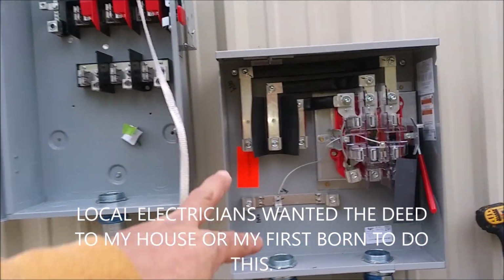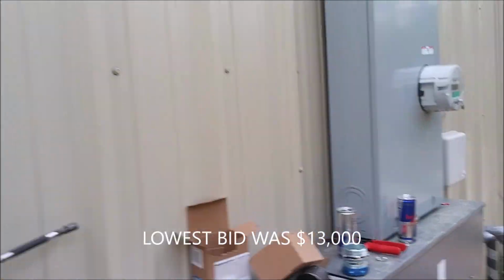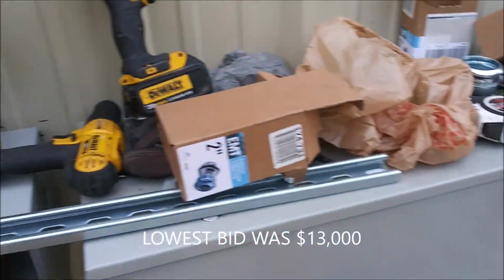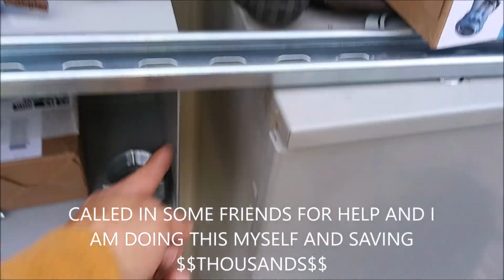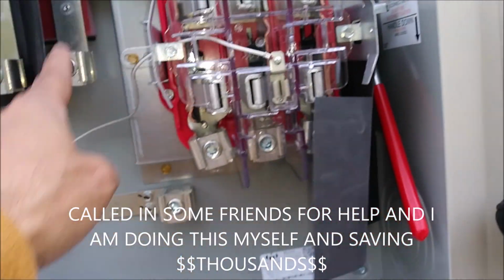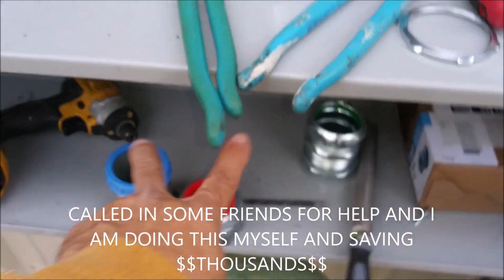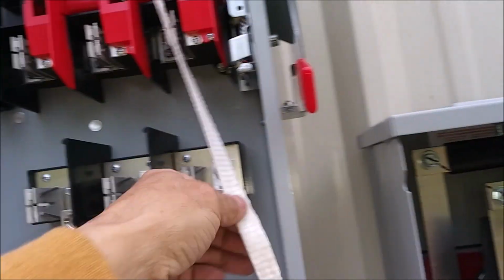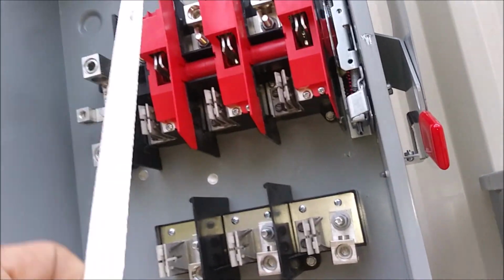We had to put in a 200 amp meter box, tie in off of this 400 amp service. The power is going to jump over to the gutter, up to the meter, down here, around this way. We're going to tap into it here, up this way, to a disconnect, 200 amp disconnect, and then fed up. We're literally right now going to feed the 3-aught cable.